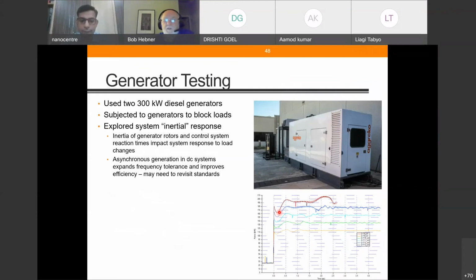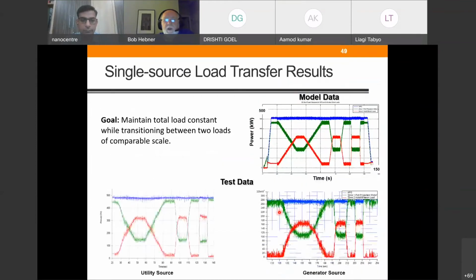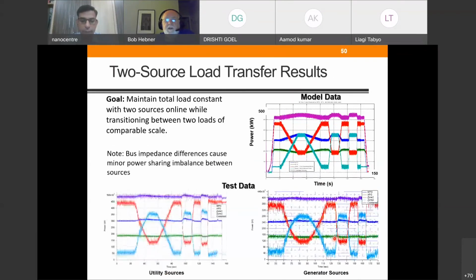We did testing with two 300 kilowatt diesel gensets that we moved in and attached to our microgrid. Basically, the bottom line is if we ran the microgrid from a utility source or from a generator, and we bounced the power between two loads without changing the total power needed, stability was easy to maintain, as predicted.